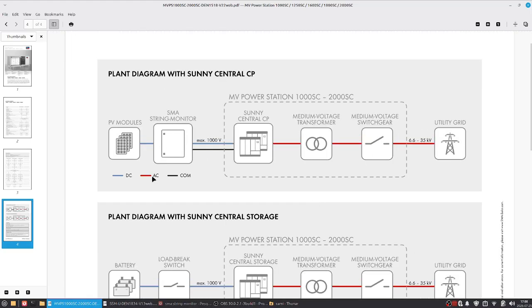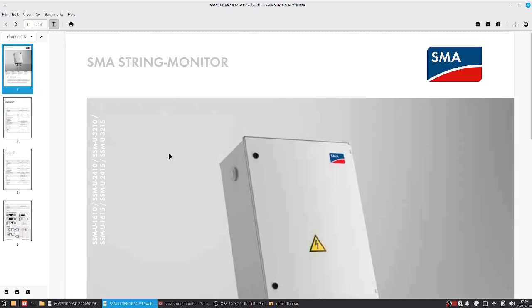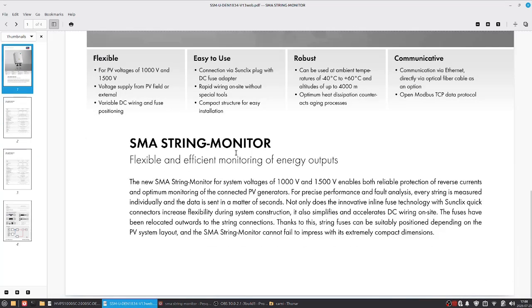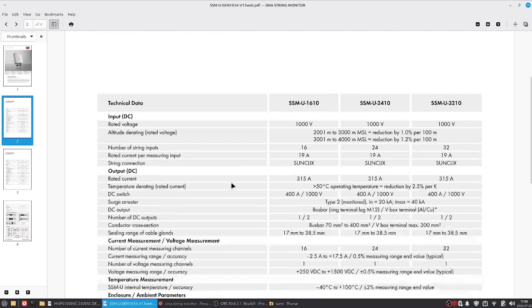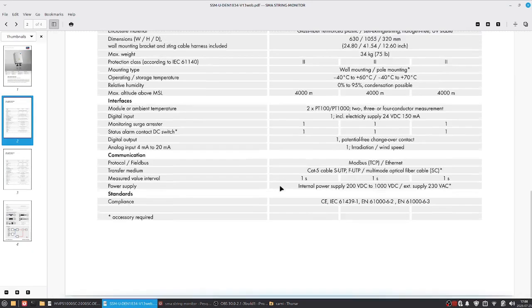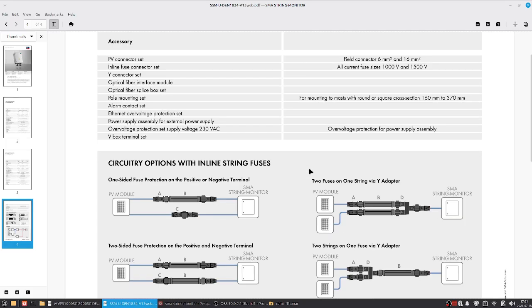Now we go to the string monitor. So we have 1250 amps. We have to see how much the string monitor will put out. The maximal output DC rated current is 315, so you need four of those to distribute the DC power to feed the power station.